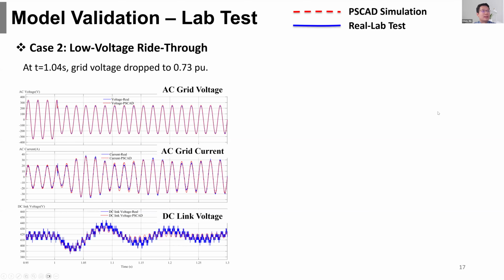So in addition, we have also tested the ride-through capability of our model. So what we do is we simulate a grid voltage sag. We drop the grid sag voltage to 0.73 per unit. So the first figure is the grid side AC voltage. We can see that the RMS value is decreased from 1 per unit to 0.73 per unit. And the second figure is the AC grid current, because it's modeled as a constant power. So with the voltage drop, we have the current increase. And the last figure is the DC link voltage. For these three figures, the red curve is our simulation results using our model, and the blue curve is the real lab testing results. We can see that the simulation and the real testing align very well.